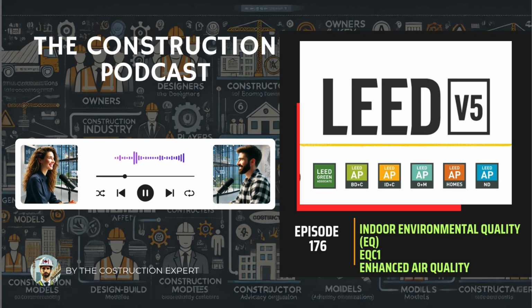Okay, so that reframes option one. It's not necessarily the easy option just because the calculation seems straightforward. It's more like the strategically expensive operational option. That's a good way to put it. Let's get specific on the delivery mechanism then. You mentioned breathing zone, outdoor air ventilation rates. What exactly are we measuring there, and why is that distinction, breathing zone, so important?